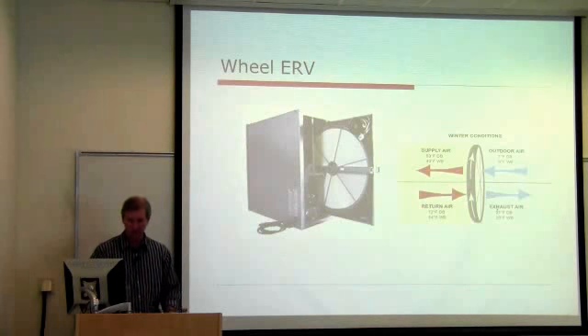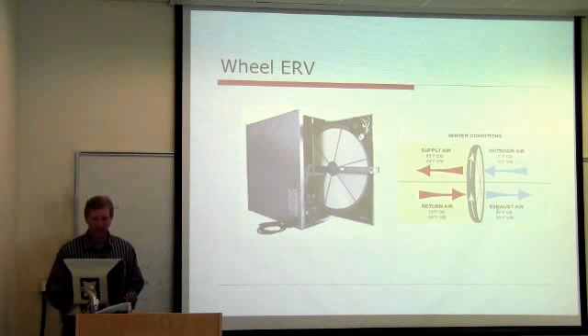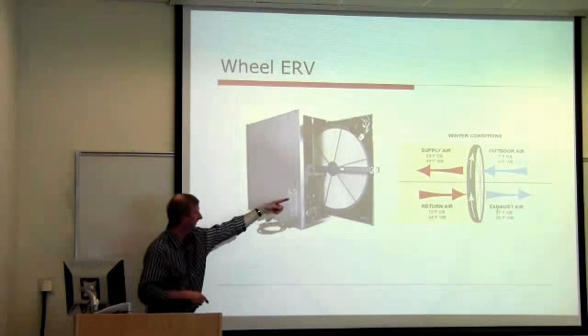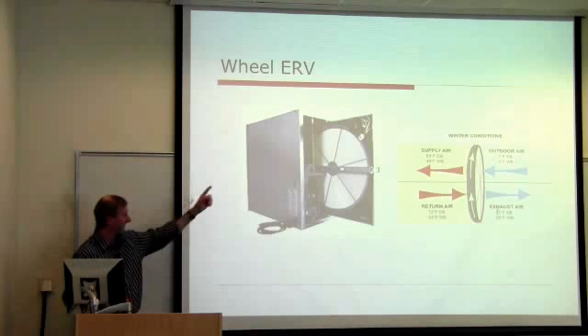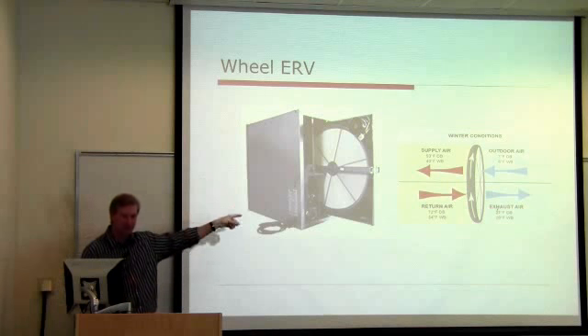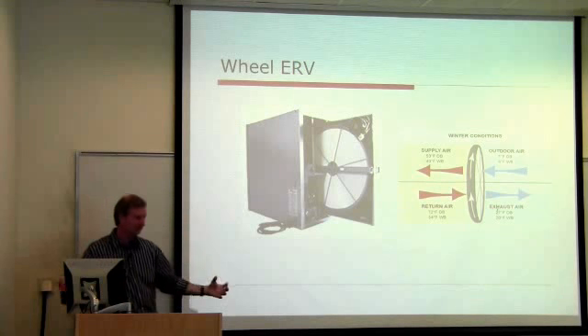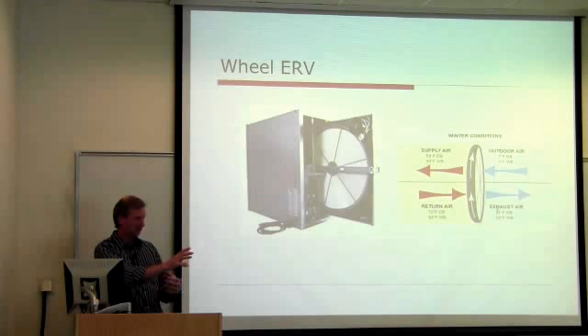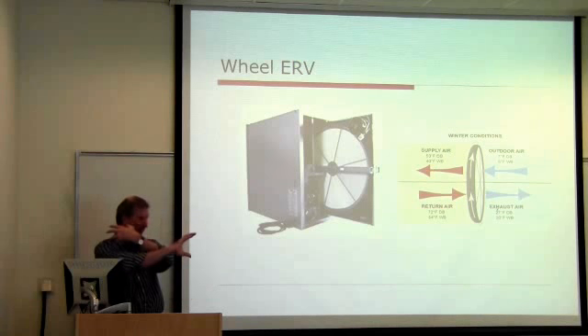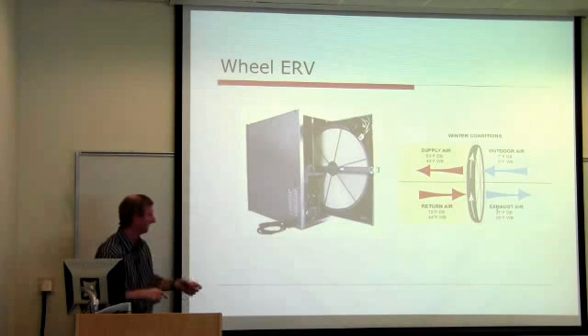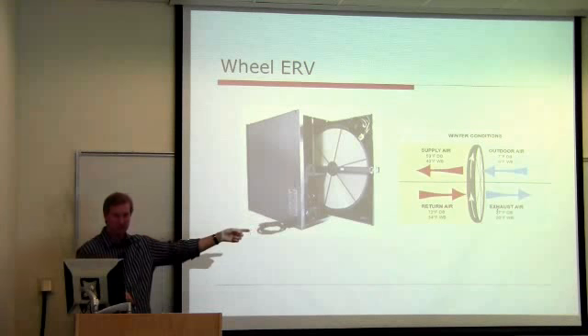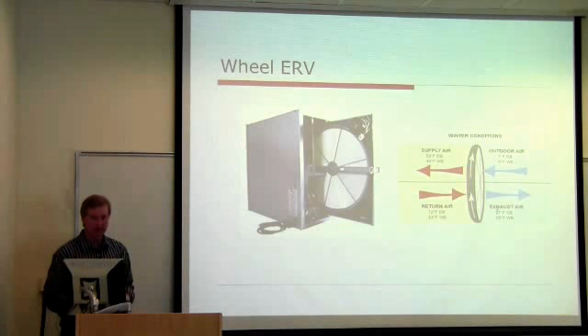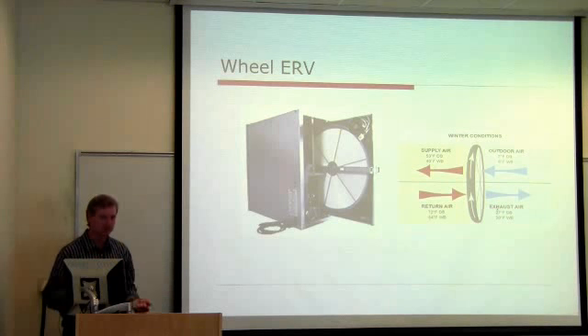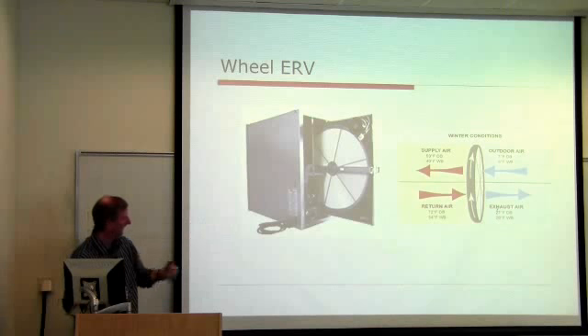And then you'll hear about wheel ERVs. I'm not an expert on these. This just has a rotating wheel with transfer material, kind of like a sponge or a foam. And as it turns, the hot air will go, and then it'll move up, and the other air will turn, so it's continuously revolving and transferring heat that way. Most of these aren't PHI or Passive House certified because of the leakage. There is some cross leakage, so you have to look at that.